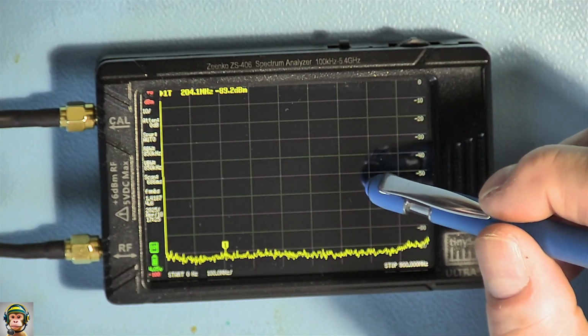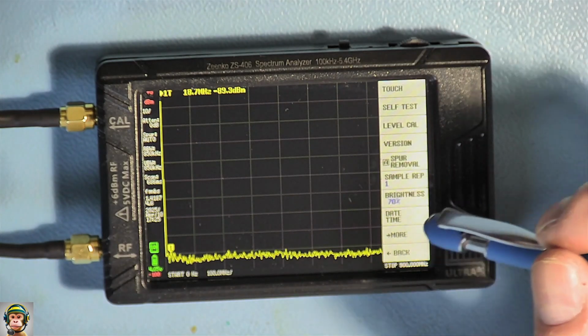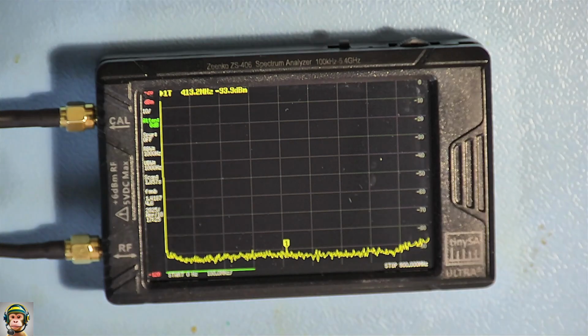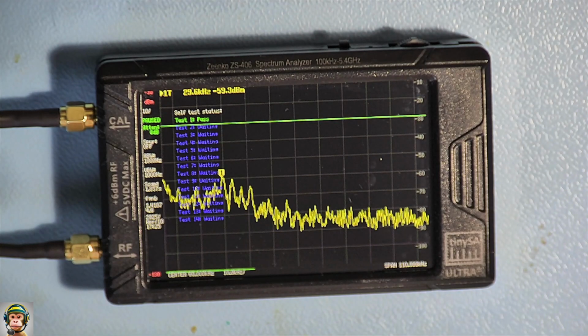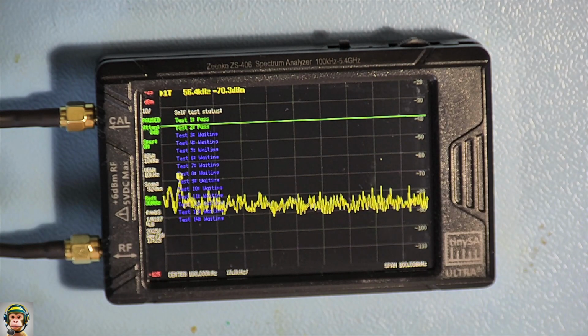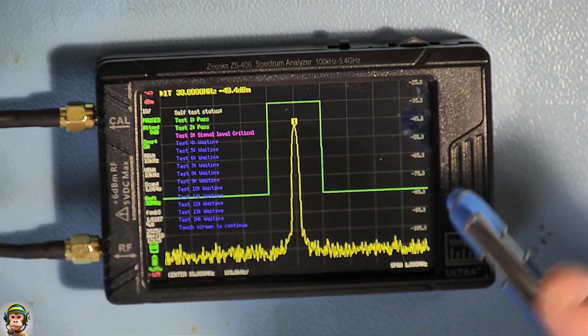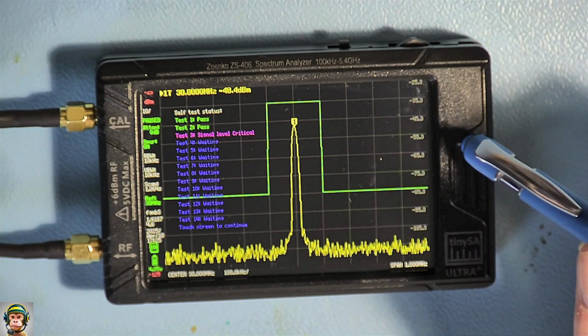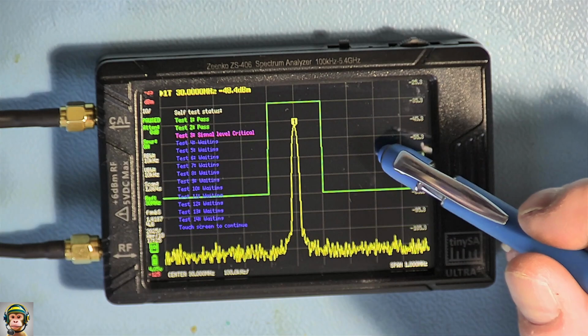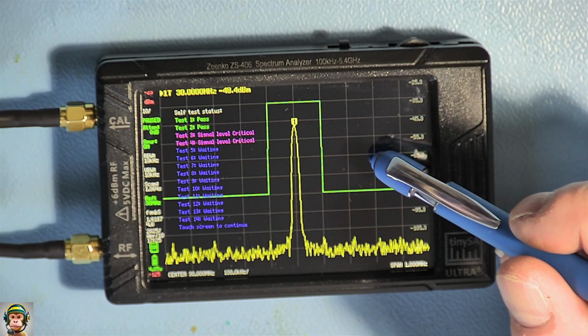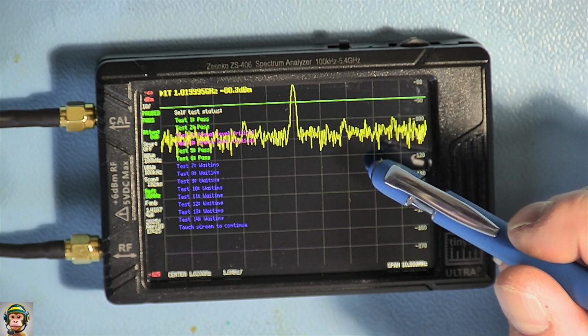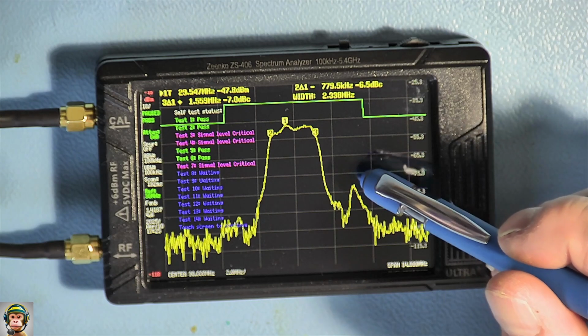I really have no clue where this happened, but I broke my TinySA Ultra. If you look at the top left corner, you see that the dBm value is in red, which means that the signal level is not calibrated anymore. When I do the self-test, it fails on multiple tests with the message signal level critical. Now what?